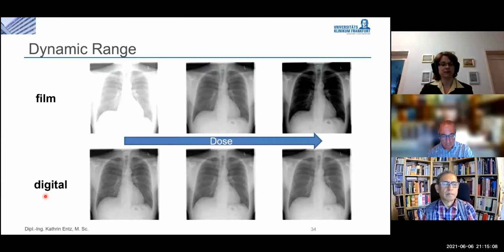And your deviation index is computed in a way that it corresponds to steps on the density or mAs control on your system. So you can see here, ideally, your deviation index should be roughly around 0. If the value is higher than 0, then it's an overexposure. If it's below 0, it's an underexposure. So what can you now do with those exposure index values?